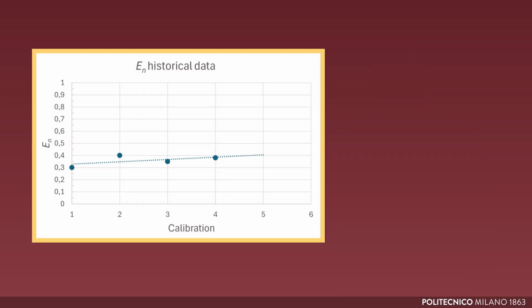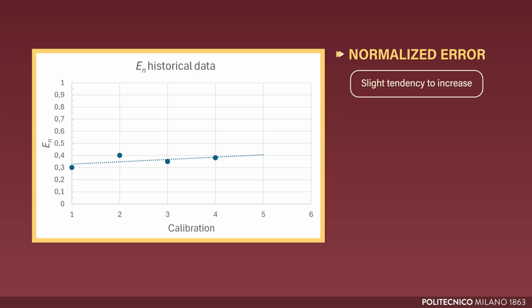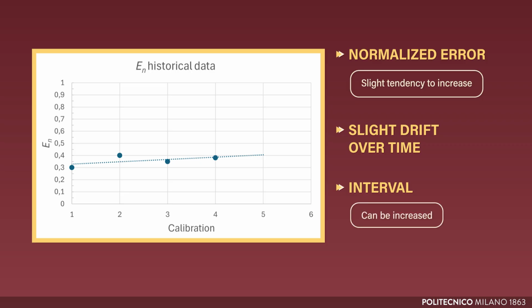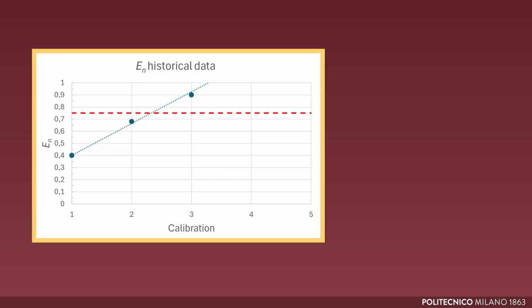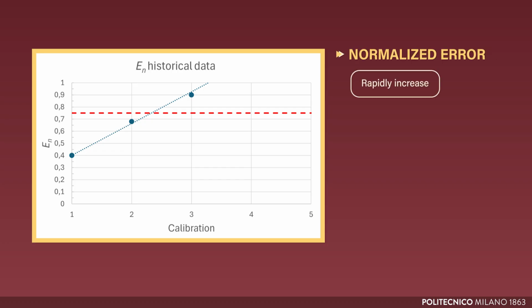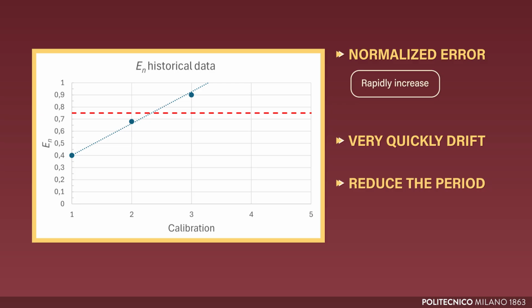Let's consider, for instance, the case shown in this figure, where the normalized error shows a slight tendency to increase between one calibration and the next, as indicated by the dashed trend line. From this, it can be assumed that the employed instrument has a slight drift over time, and the interval between two successive calibrations can be increased without risking the instrument operating outside the required metrological specifications. Let's now consider the case shown in this other figure, where the normalized error tends to increase very rapidly between one calibration and the next, and exceeds a warning threshold represented by the suitably chosen red dashed line. It can be inferred that the instrument tends to drift very quickly, and in this case, it is advisable to reduce the period between two successive calibrations.